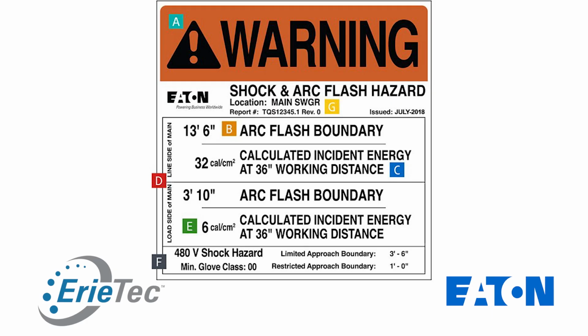Nominal voltage would be the voltage that's present at that control panel. You have to make sure that your PPE is rated for that voltage, specifically your gloves. Gloves could be 250 volt, 600 volt, 1000 volt, or even higher. So you have to make sure you have the right voltage rated gloves for the job that you're working on.